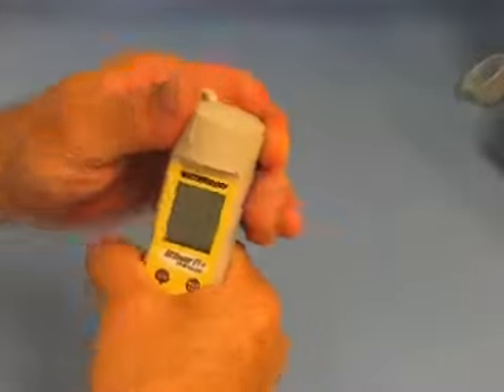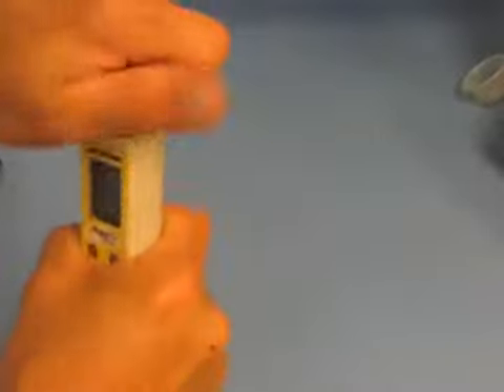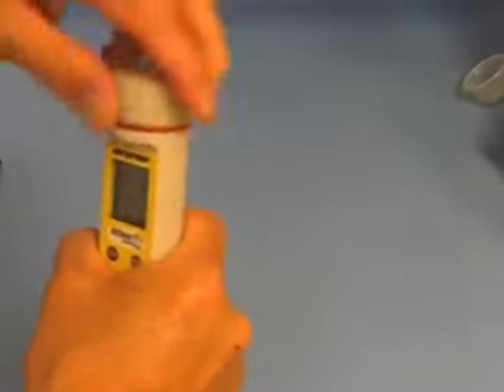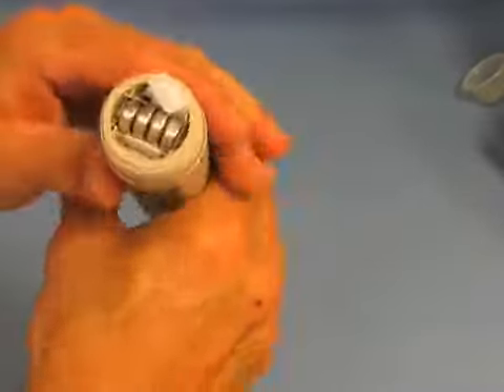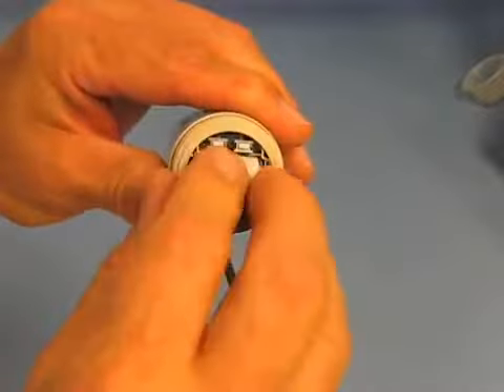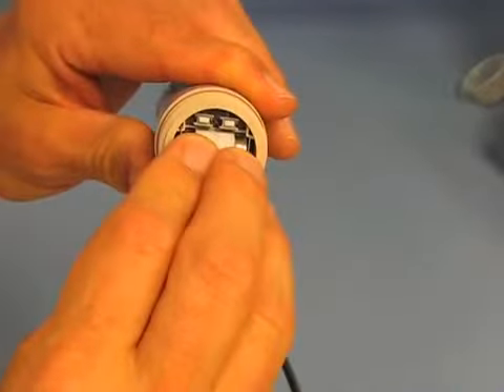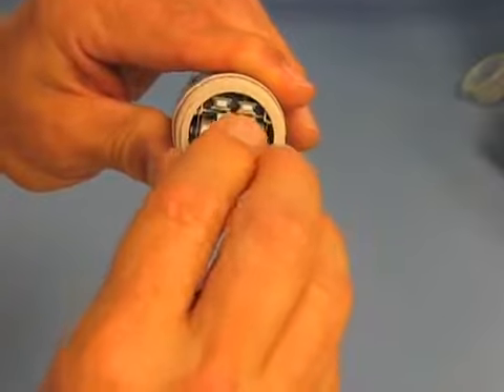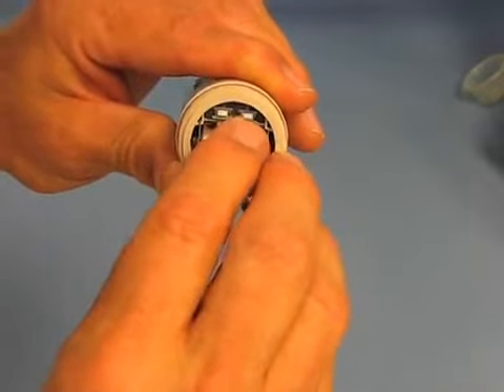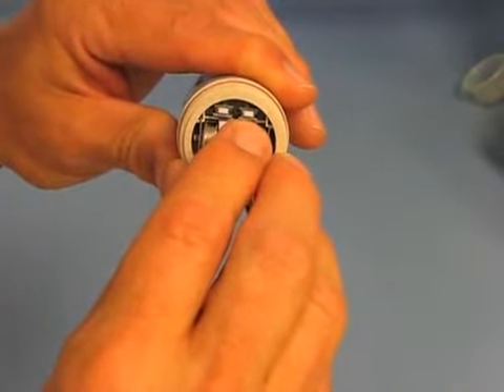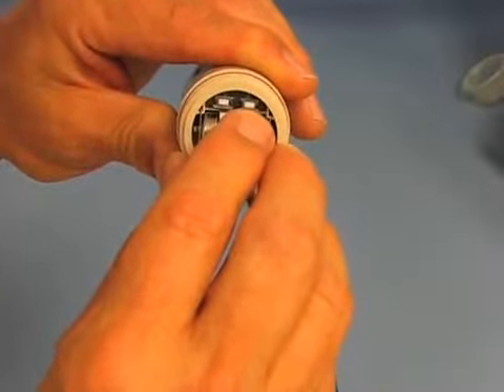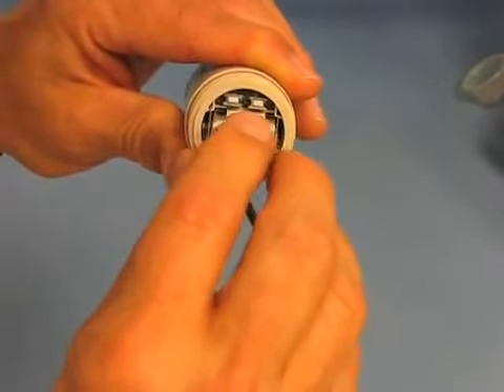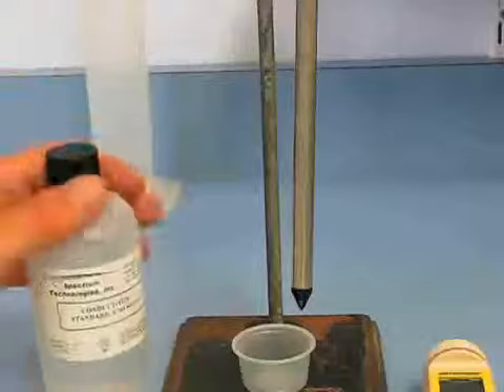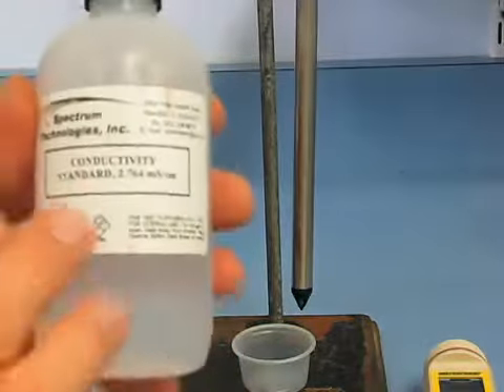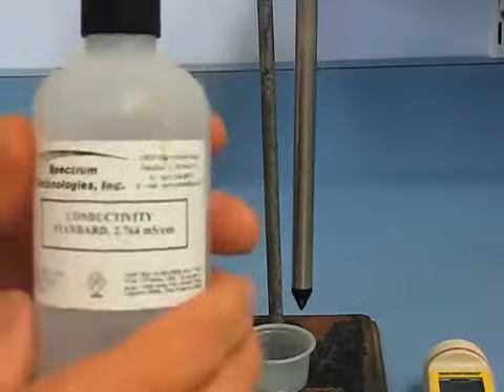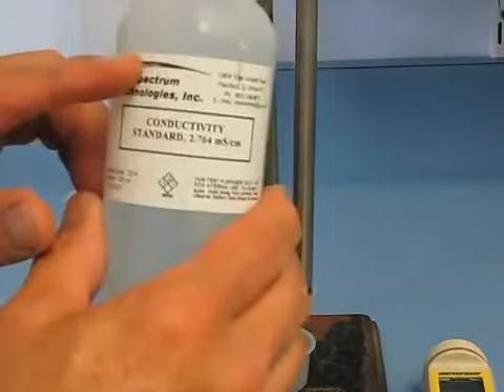To get ready to calibrate the meter, you need to unscrew the watertight cap at the top of the meter. Once the cap is removed, you'll see batteries and 2 small buttons. These buttons are used to either increase or decrease the values on the display to match the EC of the standard solution. When the meter is held with the batteries below the buttons, the button on the right increases the meter values and the button on the left decreases the meter values to match the standard solutions. Calibration is pretty easy using the standard 2.764 solution that came with the meter. You can order more of this solution as you need it.